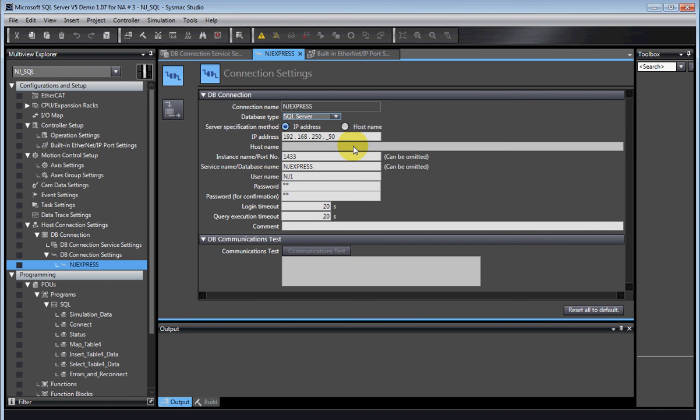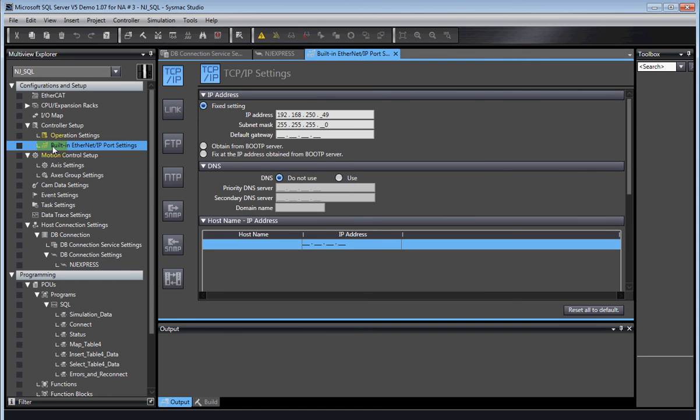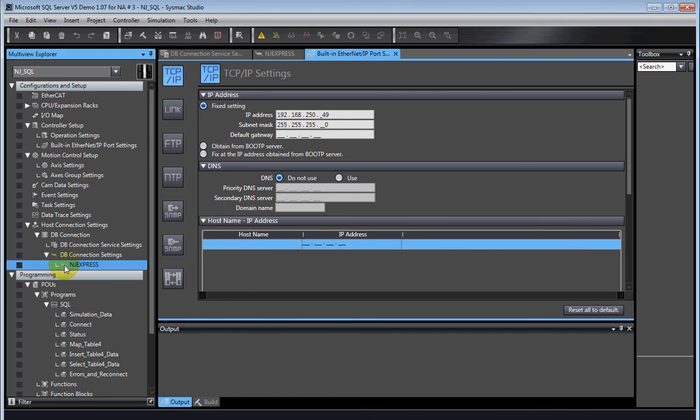The next thing is you have to tell the NJ SQL where the SQL server is, either by IP address or by host name. If you use host name, don't forget to go back to the ethernet port, turn on the DNS server, and of course tell it where the DNS server is.